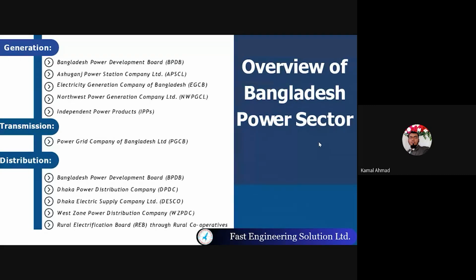If the loss is low, then the energy efficiency will be high and the energy management will be very good. If the loss is high, say if we generate 100 megawatt, but the energy loss in transmission is 5% to 10%, it will be 5 or 10 megawatt. So if the generation gets to 10,000 megawatt, then the 5% or 10% loss will be 500 to 1,000 megawatt. So it is a huge loss in the transmission sector, and there is a distribution loss also.